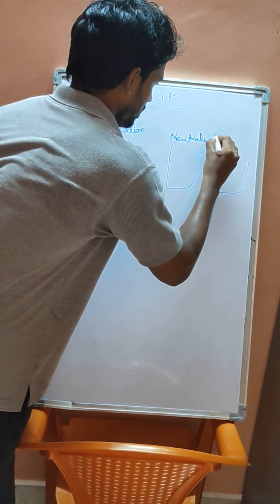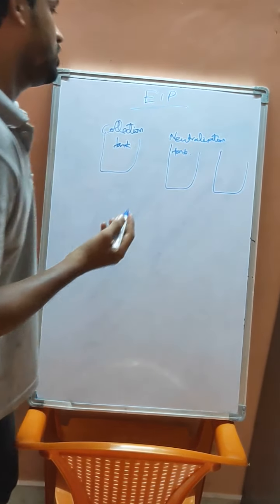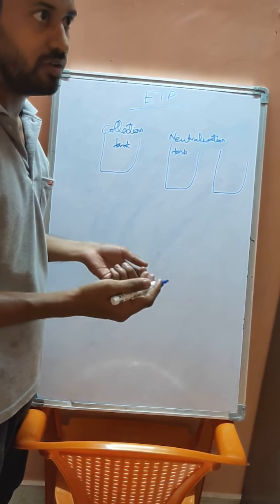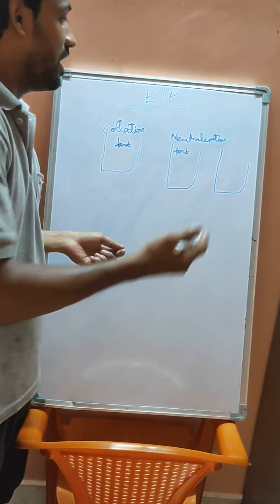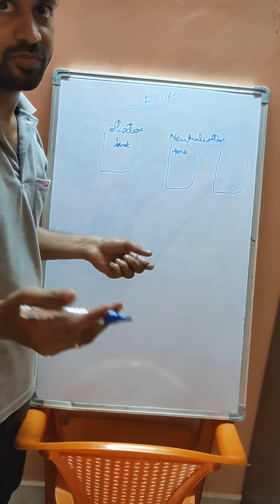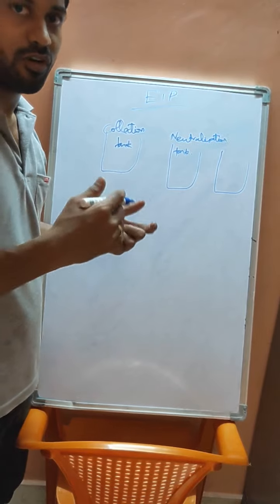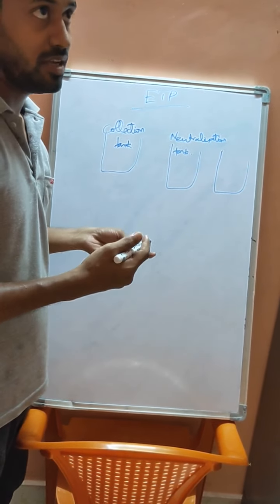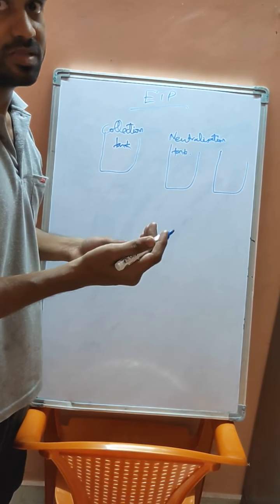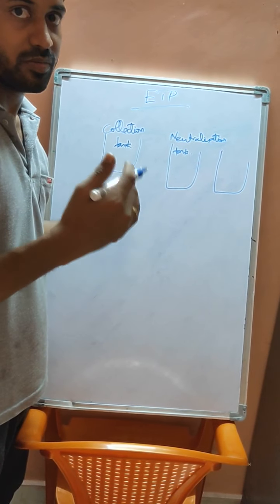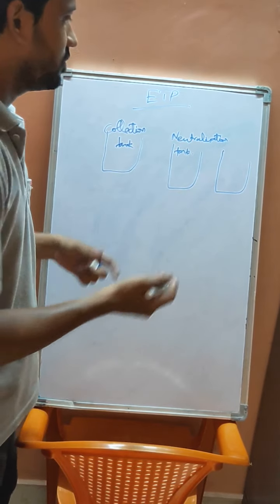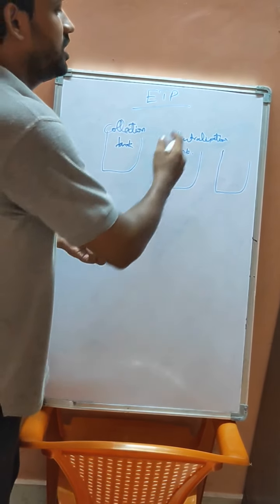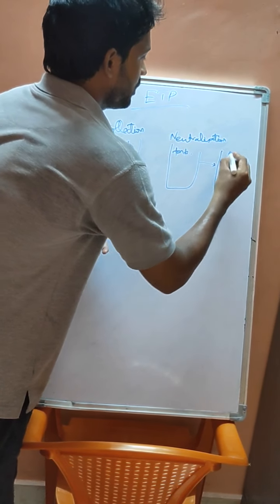From the collection tank, the effluent goes to the neutralization tank. The neutralization tank is used because the plant effluent may be acidic or basic. We need to bring the pH to around 6 to 8.5. If the effluent is acidic, we add a basic compound like ammonia or another base. If the effluent is more basic, we add acid. The pH range should be around 6 to 8.5, not exactly 7.